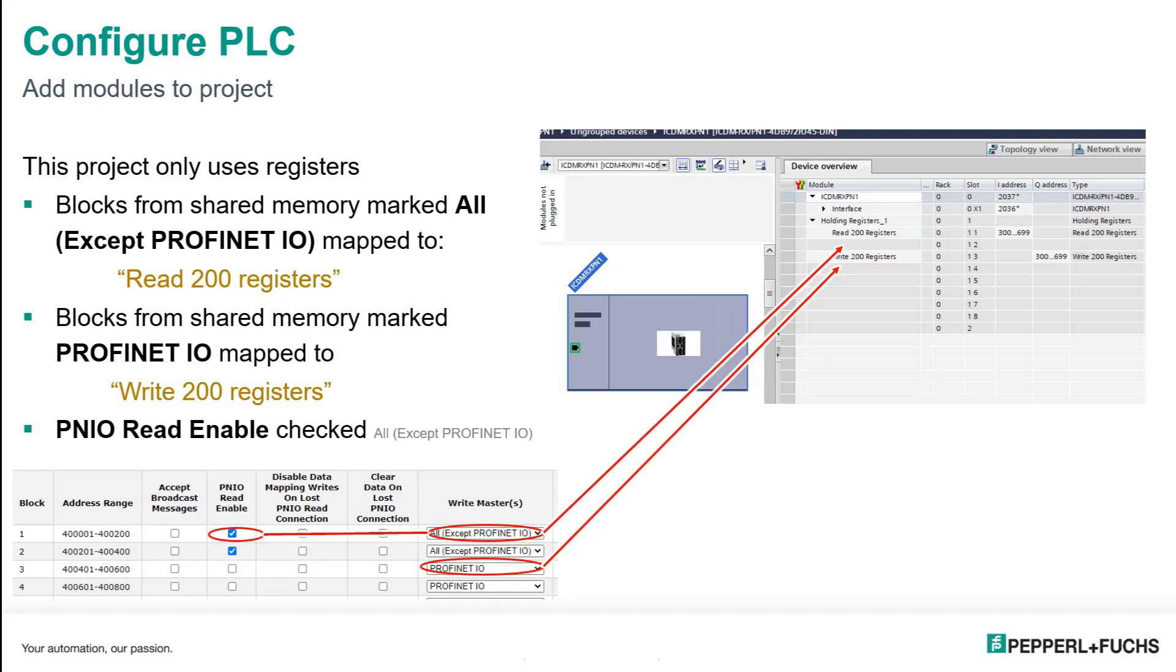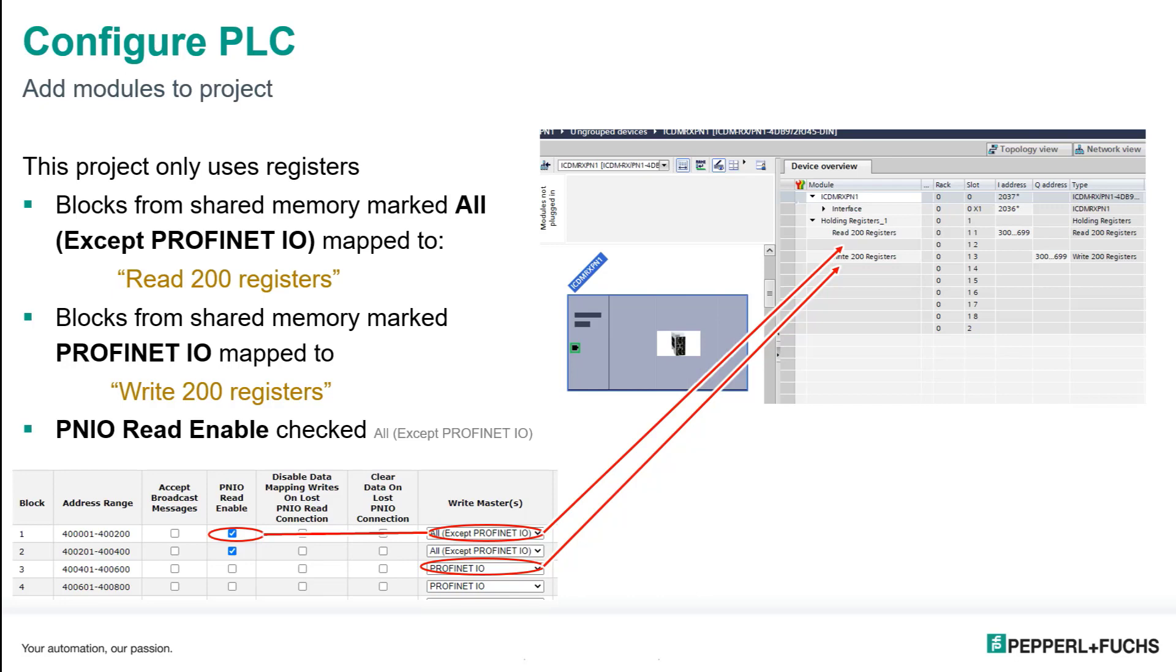So in my project, this is TIA Portal, I want to exchange really only 16 registers of input, 16 registers of output. So I'm just using registers. So I add my registers and I just want one set of 200 registers for read and one set of 200 registers for write. And you can see here, the last thing is make sure that the PNIO Read Enable that checkbox is selected anytime where you're putting inputs directly into the PLC.